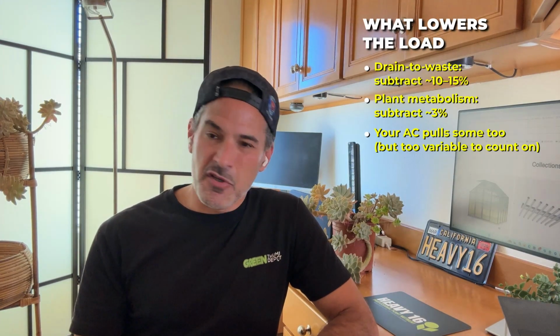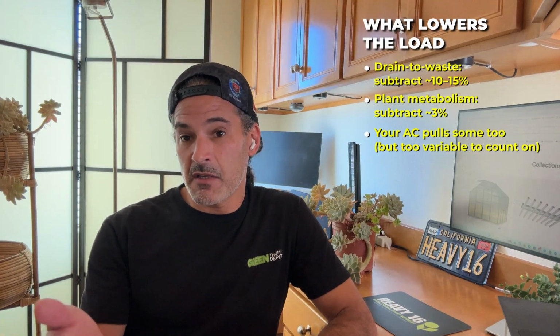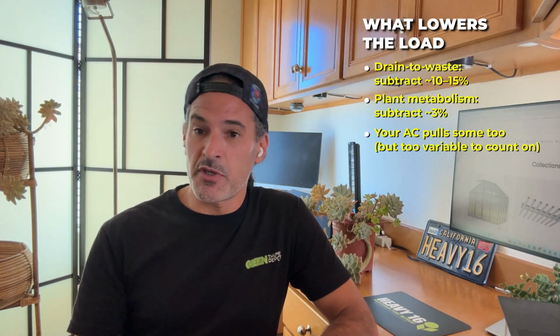It depends on the efficiency of the air conditioning equipment. Actually, more efficient air conditioning will remove less moisture because it's more optimized to cool, and less efficient air conditioners will actually function a bit more like a dehumidifier. So because of these variables, I tend to leave that out unless a customer requests it and they know the exact value of their air conditioning system and how much that can remove.